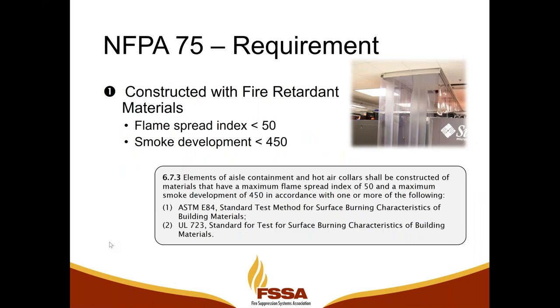Requirement number one is that aisle containment partitions are constructed with fire retardant materials. Those materials need to have a flame spread index of less than 50 and a smoke development index of less than 450. So ultimately NFPA 75 and 76 limit the materials that can be used, as the materials in your aisle containment system have to meet these flame and smoke spread ratings, which you will know if you understand much about plenum rated materials. These are less stringent than what can be provided in a plenum and be plenum rated.